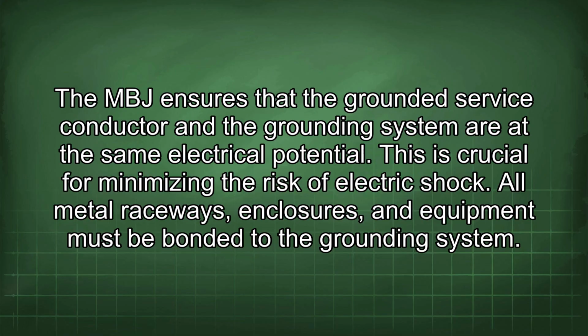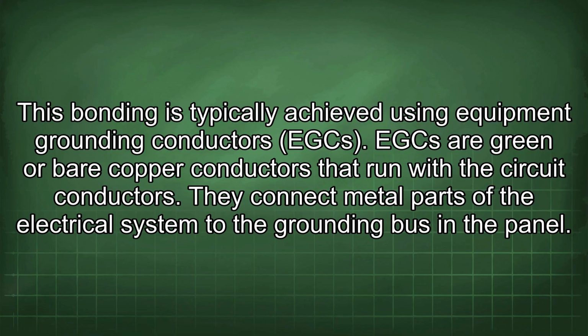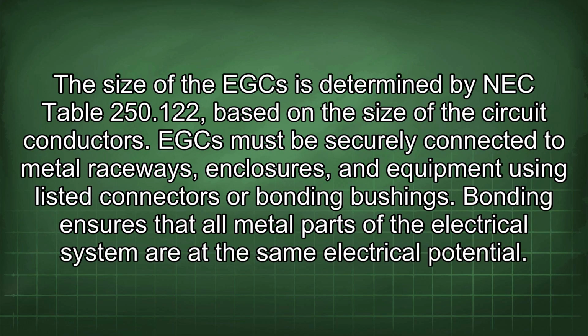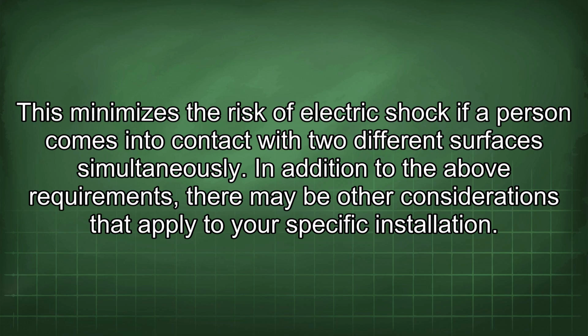All metal raceways, enclosures, and equipment must be bonded to the grounding system. This bonding is typically achieved using equipment grounding conductors, EGC. EGCs are green or bare copper conductors that run with the circuit conductors. They connect metal parts of the electrical system to the grounding bus in the panel. The size of the EGC is determined by NEC table 250.122 based on the size of the circuit conductors. EGCs must be securely connected to metal raceways, enclosures, and equipment using listed connectors or bonding bushings. Bonding ensures that all metal parts of the electrical system are at the same electrical potential. This minimizes the risk of electric shock if a person comes into contact with two different surfaces simultaneously.